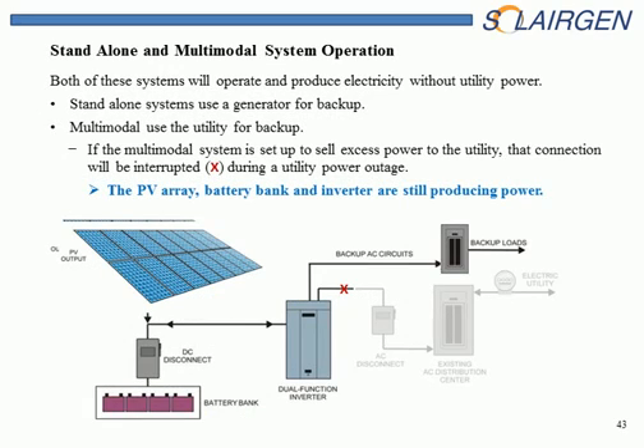So the standalone and the multimodal system operation, if the AC is disconnected on a multimodal system, this part of the system is still operating. So here's the backup loads in a multimodal system. It's always feeding power to this panel, and unless you can get to that AC disconnect, the AC power as well as the DC power are present in this PV system.